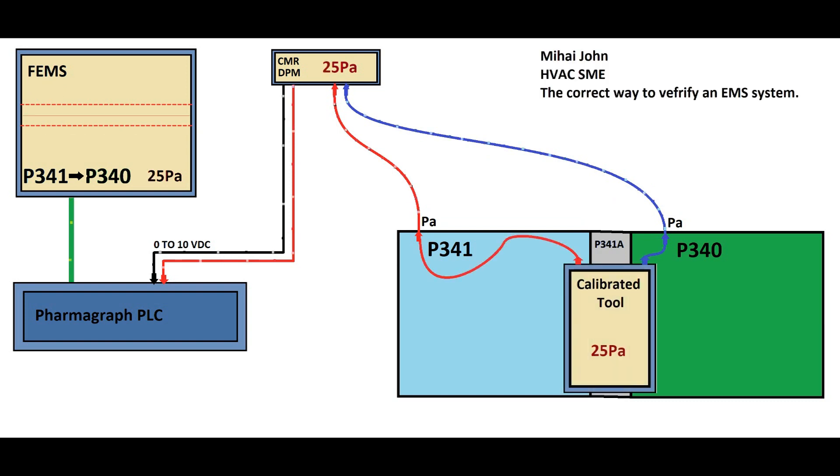This test involves connecting the calibrated tool to the room's tube, allowing comparison of data readings between the calibrated tool and the PharmaGraph front-end panel. Successful alignment in data readings validates the accuracy and reliability of FEMS.